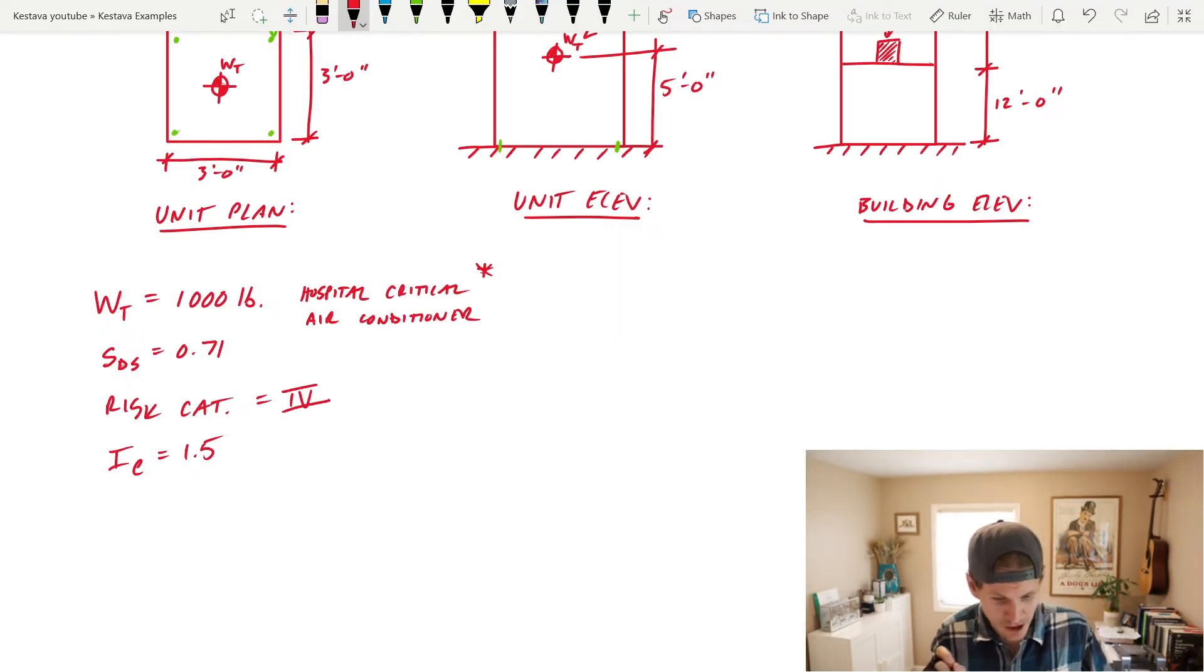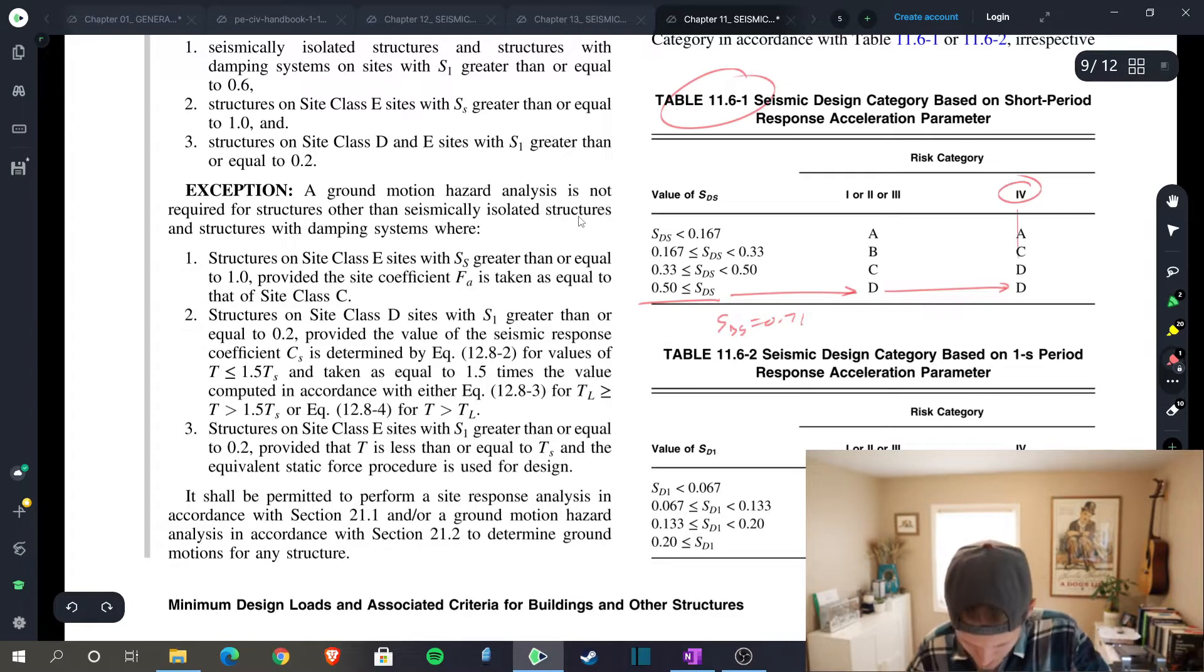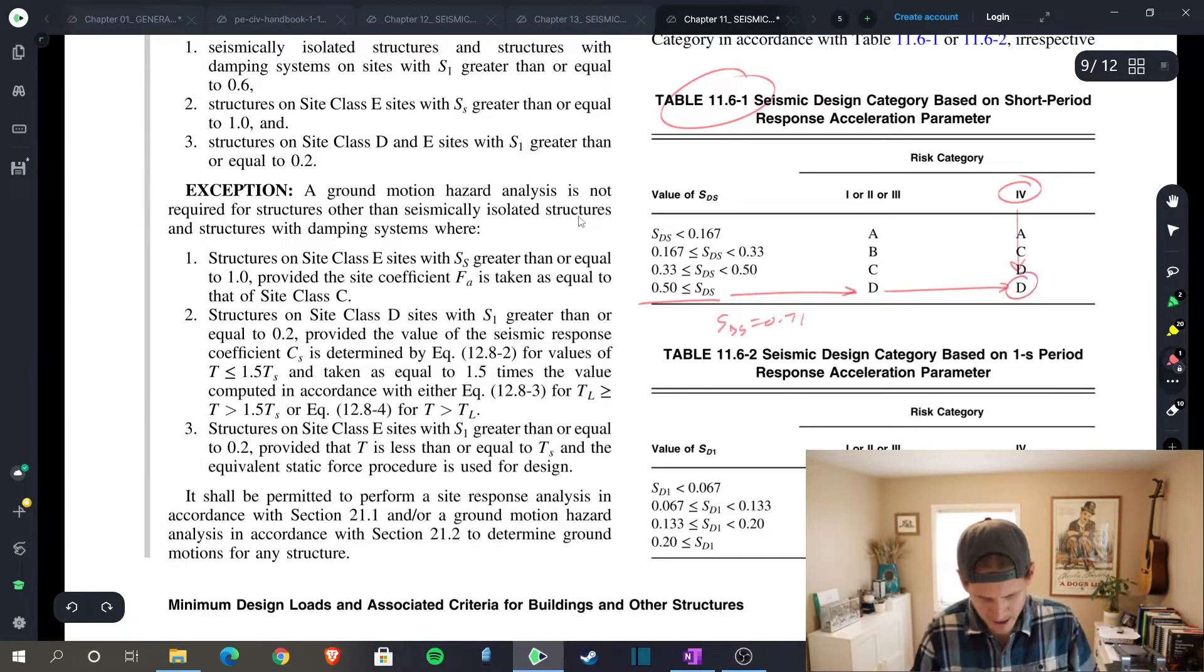Let's now head over to chapter 11 to determine our seismic design category. Table 11.6, we're doing just that. We know we have an SDS equal to 0.71, which means that we fall under this criteria, and we know we've determined a risk category 4, which means that we fall under seismic design category D.